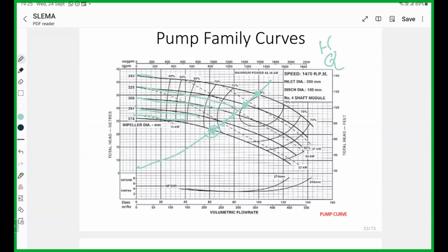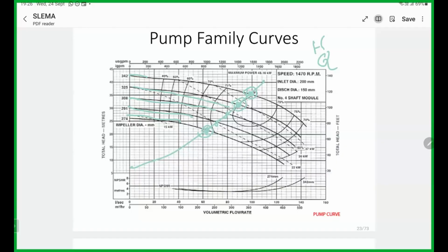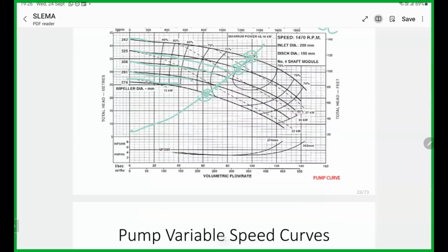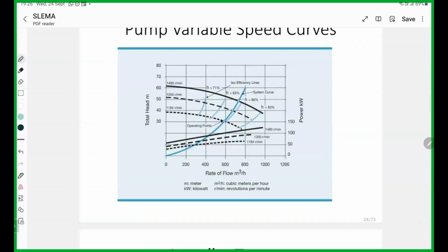We cannot say what the performance of this pump is, because sometimes one pump has a larger impeller, the same housing, the same appearance, but the other one has another performance. Those two pumps are not identical, always not identical, right? It depends on the impeller diameter, right? Family curve. Then we have RPM curves. Then the pump curve is here.